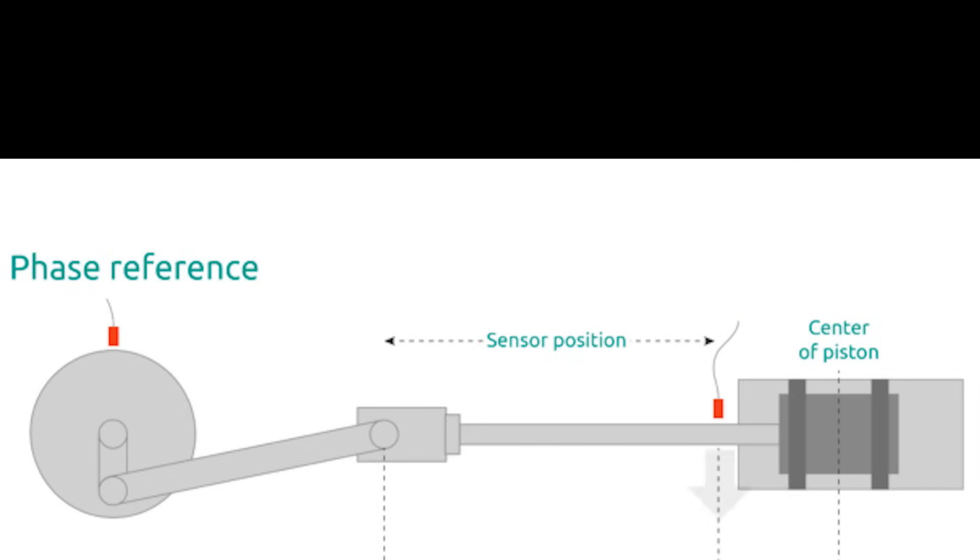As wear occurs, the shaft will drift in relation to the probe, producing a change in voltage. This measurement is typically taken in conjunction with a key phaser measurement. The key phaser is used to ensure the crank is in a specific orientation each time the rod drop measurement is captured.